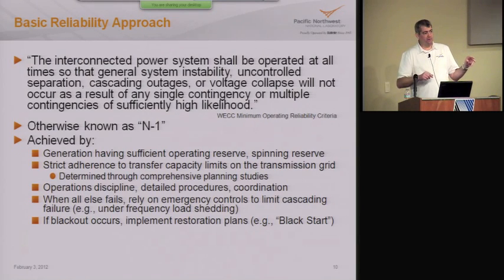Hydro is a great example of that. It doesn't take much energy to get that going, and then you use that power to feed your other power plants and get them started, and then you can start picking up load. You can't just jump straight to adding load to the system, because you've left out the power plants you need to bootstrap the system back up. It was the '65 blackout that taught us the hard way that you need a good solid black start plan that's drilled and practiced, not made up as you go.